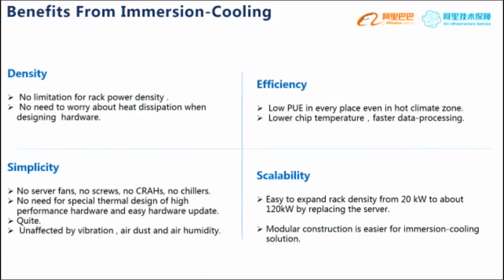To sum up, there are four benefits from immersion cooling. The first is density. When someone is designing the hardware, there is no need to worry about the thermal issue, and no limitation for rack power density in data centers. The second is efficiency. We can get a low PUE in every place, even in hot climate zones. Of course, the liquid lowers chip temperature and makes the CPU compute faster.